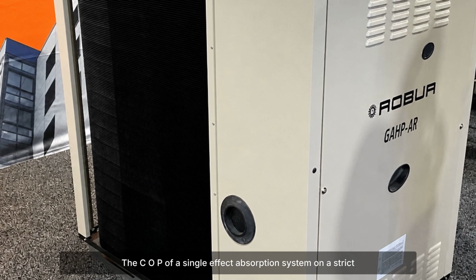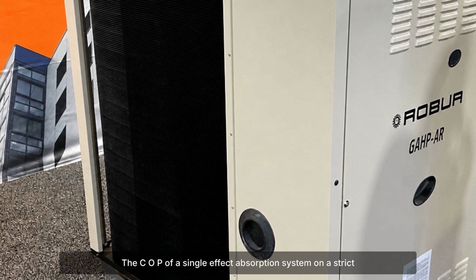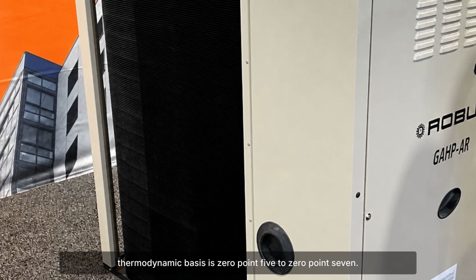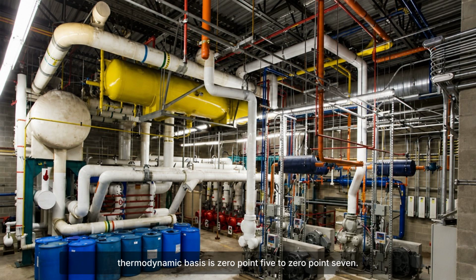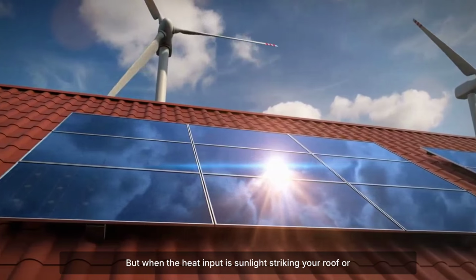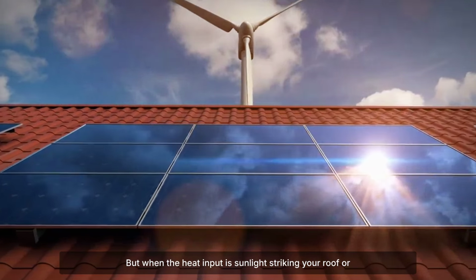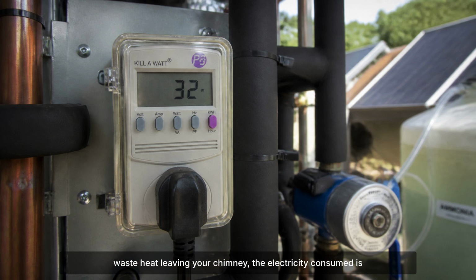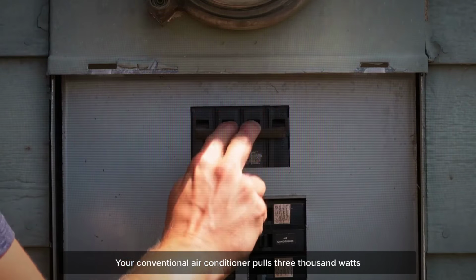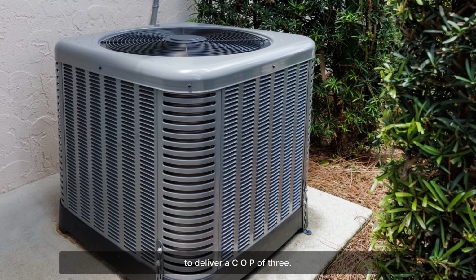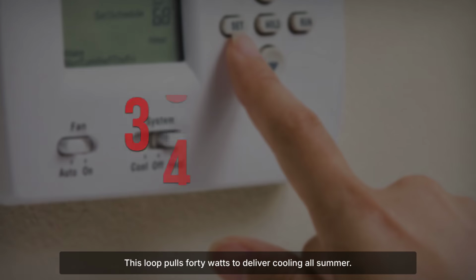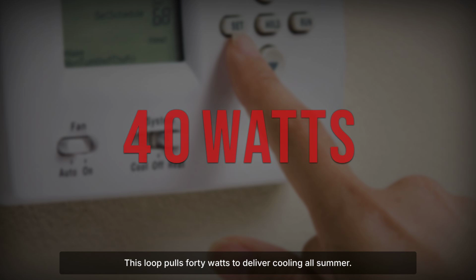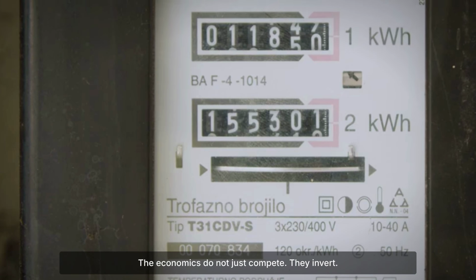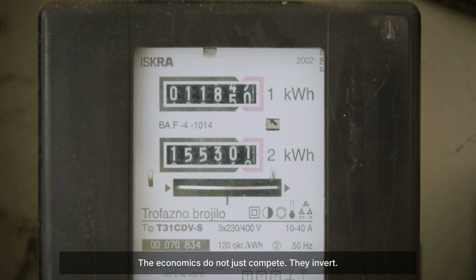The COP of a single-effect absorption system on a strict thermodynamic basis is 0.5 to 0.7, lower than a compressor, but when the heat input is sunlight striking your roof or waste heat leaving your chimney, the electricity consumed is 15 to 40 watts. Your conventional air conditioner pulls 3,000 watts to deliver a COP of 3. This loop pulls 40 watts to deliver cooling all summer. The economics do not just compete, they invert.